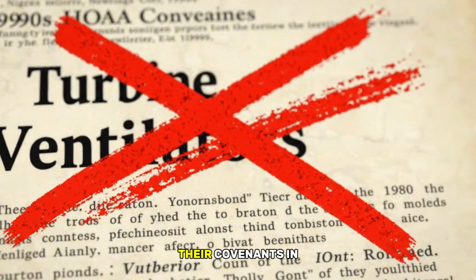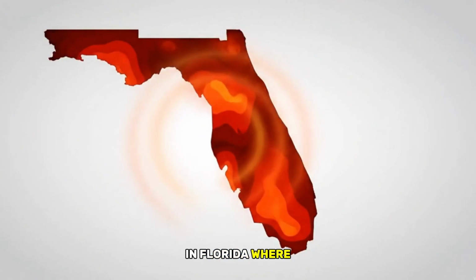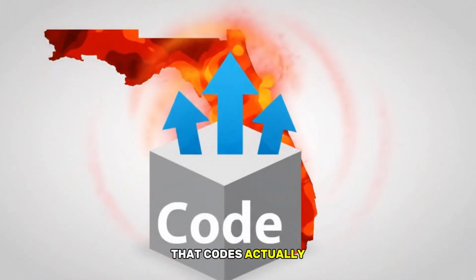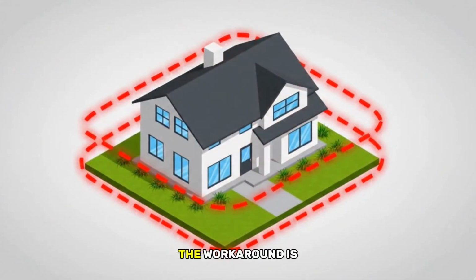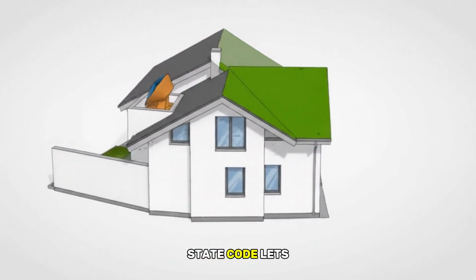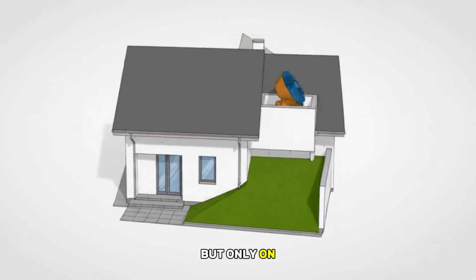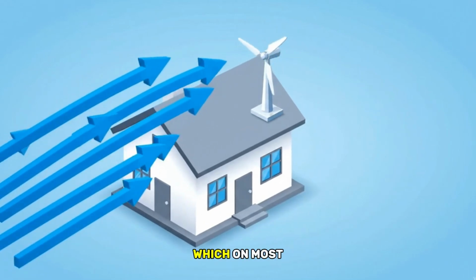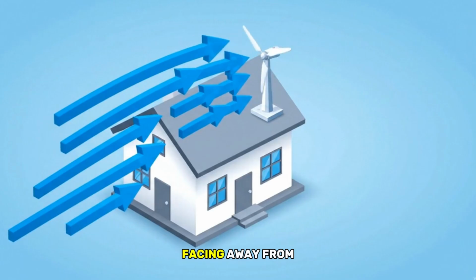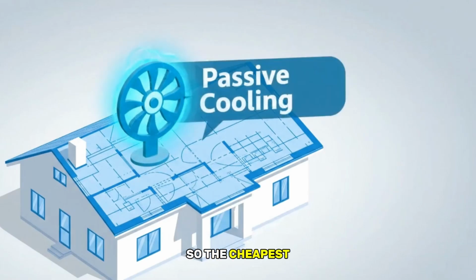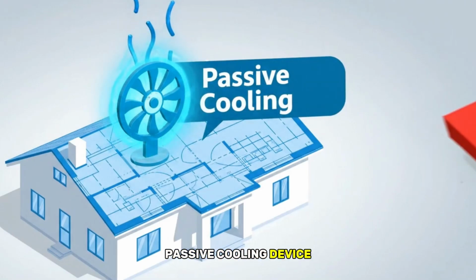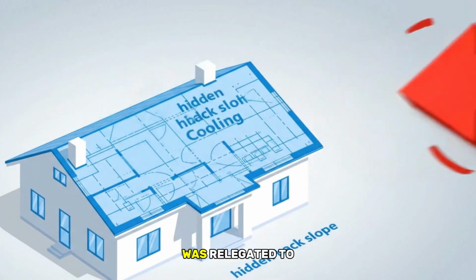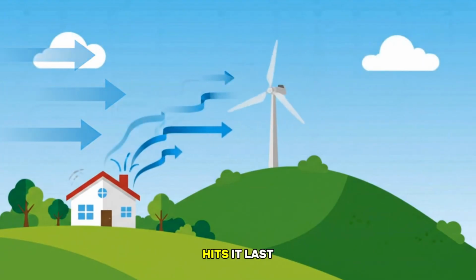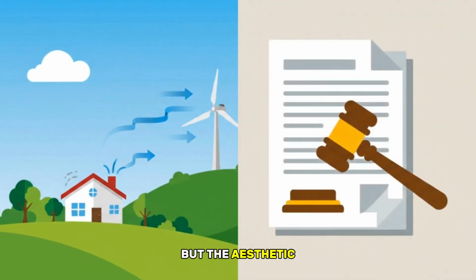HOAs across the country wrote turbine ventilators directly out of their covenants in the 1990s. In Florida, where the heat load is so brutal that codes actually demand passive ventilation, the workaround is comically restrictive. State code lets you install a turbine, but only on the rear roof slope. The rear slope, which on most homes is the slope facing away from the prevailing wind. So the cheapest, most effective passive cooling device ever invented for residential use was relegated to the slope of your roof where the wind hits it last and weakest. But the aesthetic ban is only half the story. The other half is regulatory.